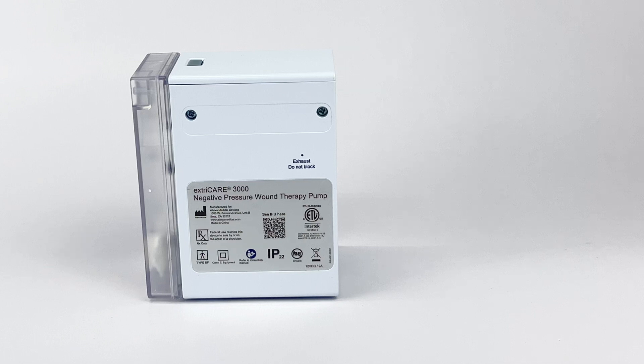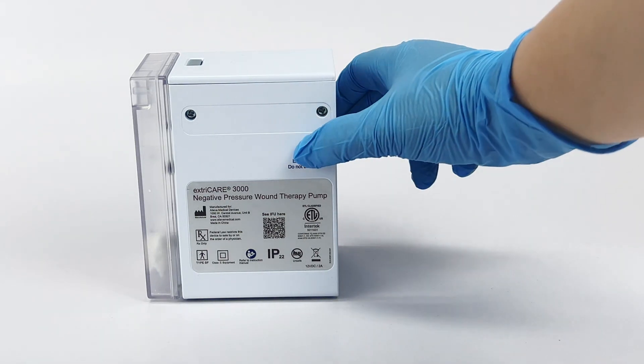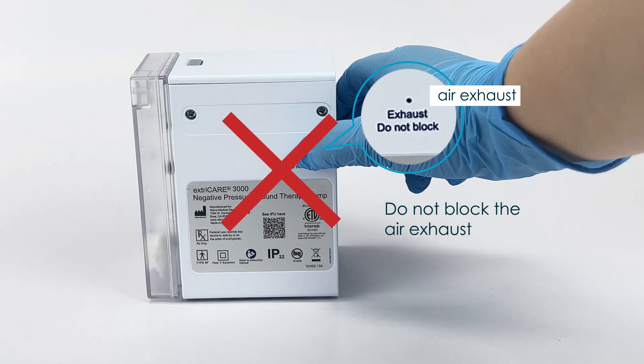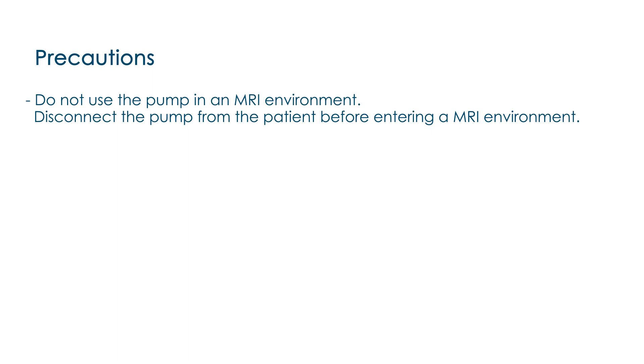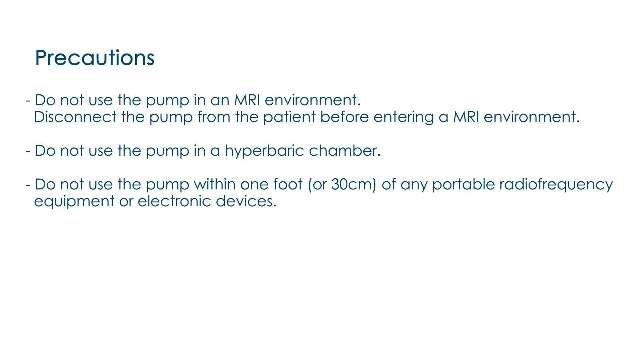Precautions. There are some precautions for using the extriCARE 3000. First, when using the device, do not block the air exhaust at the back. Blocking the air exhaust could shorten the pump life and cause the pump to overheat. Secondly, the extriCARE 3000 pump is not MRI safe. Disconnect the pump from the patient before entering an MRI environment. The extriCARE 3000 should also not be used in a hyperbaric chamber. Do not use the extriCARE 3000 within 1 foot or 30 centimeters of any portable radiofrequency equipment or electronic devices, as there could be interference that may affect the pump.